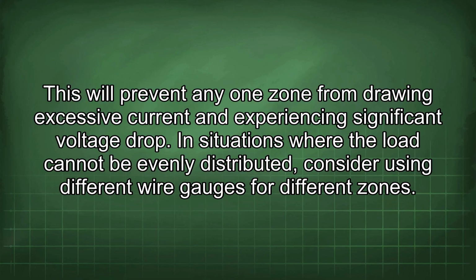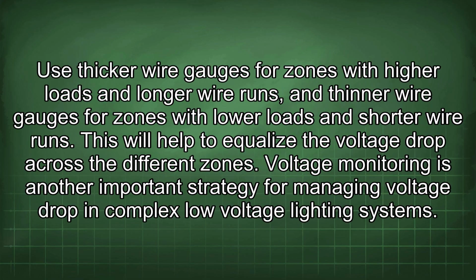In situations where the load cannot be evenly distributed, consider using different wire gauges for different zones. Use thicker wire gauges for zones with higher loads and longer wire runs, and thinner wire gauges for zones with lower loads and shorter wire runs. This will help to equalize the voltage drop across the different zones.